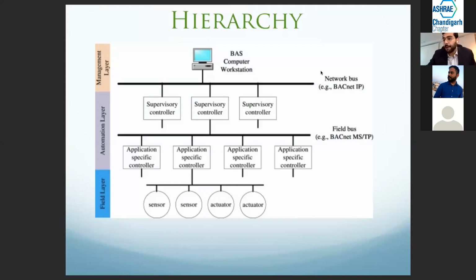BACnet works in a couple of ways. One is MSTP, and one is IP, which is over Ethernet. Now, if it is MSTP, there is a physical wire that goes from the system level controller to the first unitary, to the second, to the third, fourth, fifth, and it's like a big link. That link is called daisy chaining, okay?